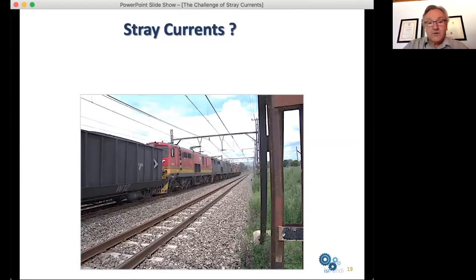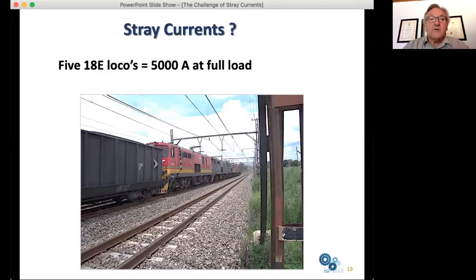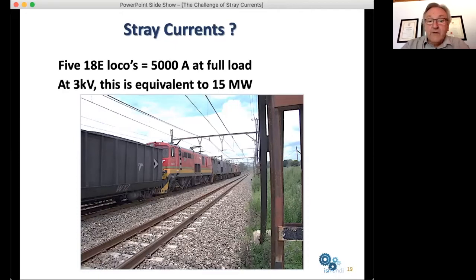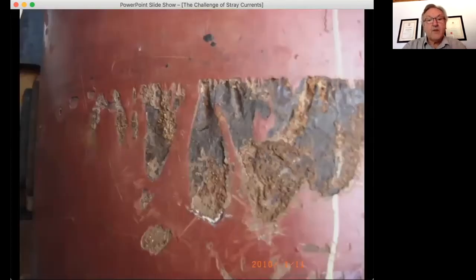So in this particular situation, which is a heavy haul DC traction system, we have 5 locos up at the front. Each loco is rated at something like 1 megawatt, and we have a total of something like 5,000 amps that is drawn through those rails. At 3 kV, 3,000 volts, which is the operating voltage of the system, that is equivalent of 15 megawatts of power. That's a lot of power. So when that gets into the ground and travels through an unintended path, particularly in the form of a pipeline, we have some interesting challenges, such as this.